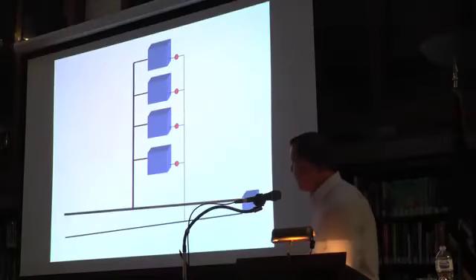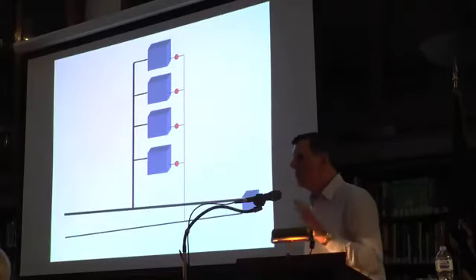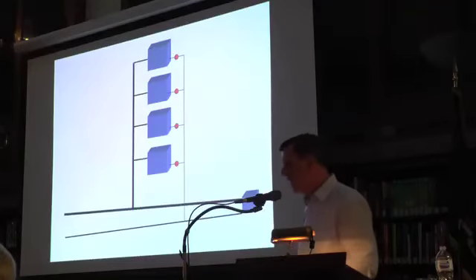But now let's say one of those traps goes bad. Let's say it's the trap on the first floor. It goes bad, it fails in the open position. It's not going to call you to say, listen, I'm not working anymore. Because that trap in a typical New York City apartment building is cycling 350,000 times a heating season. So manufacturers of traps give them 10 years tops. They get replaced every 50 years, if they're lucky. Right? So traps fail, they're open, and they're passing steam into the return.